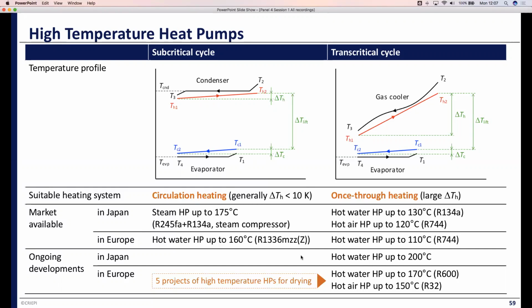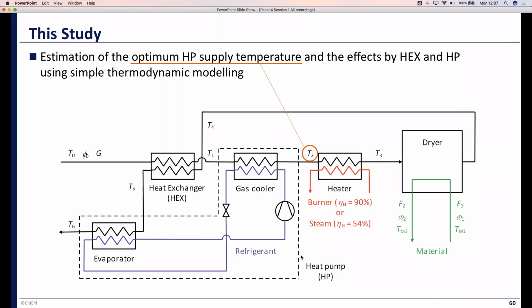Regarding the development trend of transcritical heat pumps, now in Japan, hot water supply heat pumps up to 130 degrees C and hot air supply heat pumps up to 120 degrees C are market available. In Europe, hot water supply heat pumps up to 110 degrees Celsius are market available. And in Japan, two manufacturers are developing high temperature heat pumps up to 200 degrees Celsius. Also in Europe, some projects are developing high temperature transcritical heat pumps, mainly targeting drying processes. In this way, the development of high temperature heat pumps has been progressing steadily.